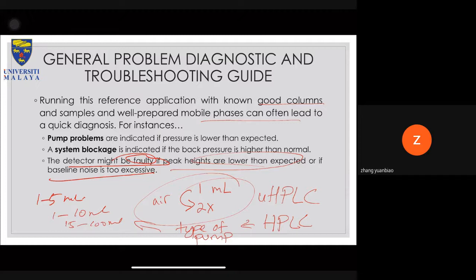You might want to change it, but the practice that I normally follow is to remove the column and then run the pump at twice the flow rate that I normally use. So if I normally do 1, then I will do 2 mL. If I normally do 5 mL, then when flushing out the air bubbles, I will do 10 mL per minute.